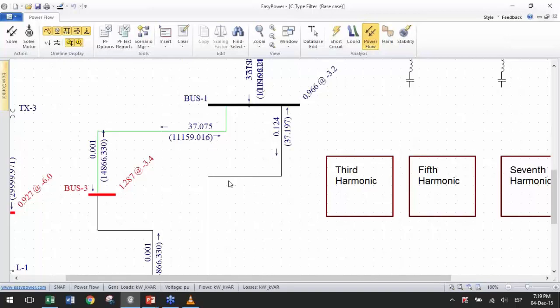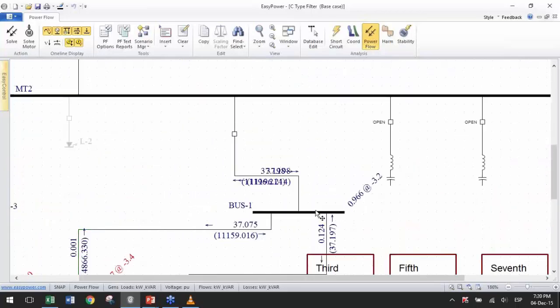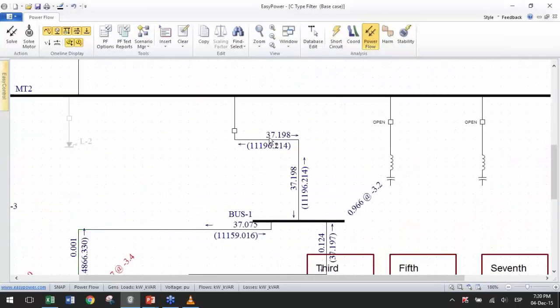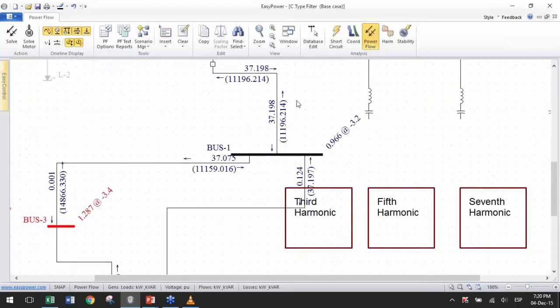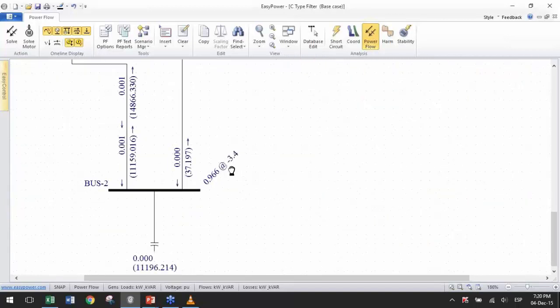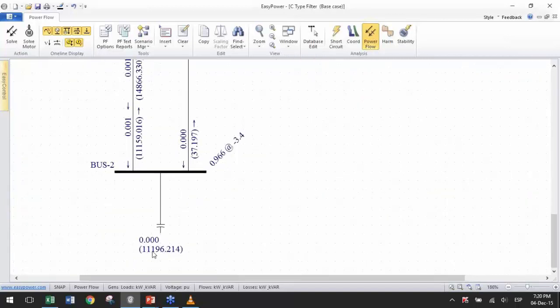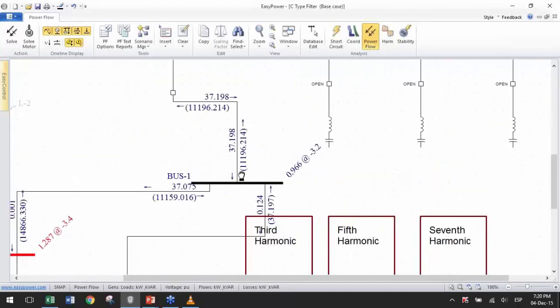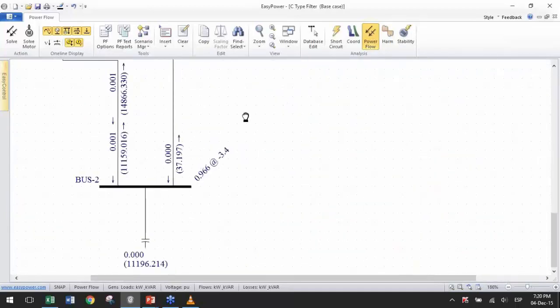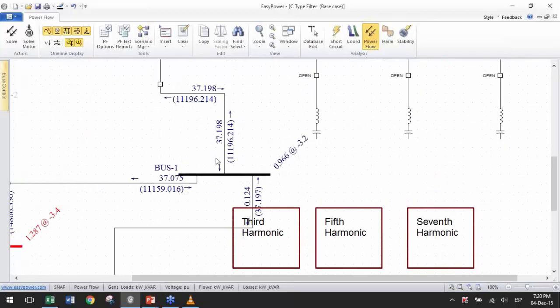This branch and this branch are in parallel. Therefore, the current will split. Necessarily, some power will flow through here. But in the end, this filter is producing in here for the system the exact same amount of MVARs that are coming out of the capacitor. 11.196 are going out of the capacitor and into the system. So power-wise, the filter works.